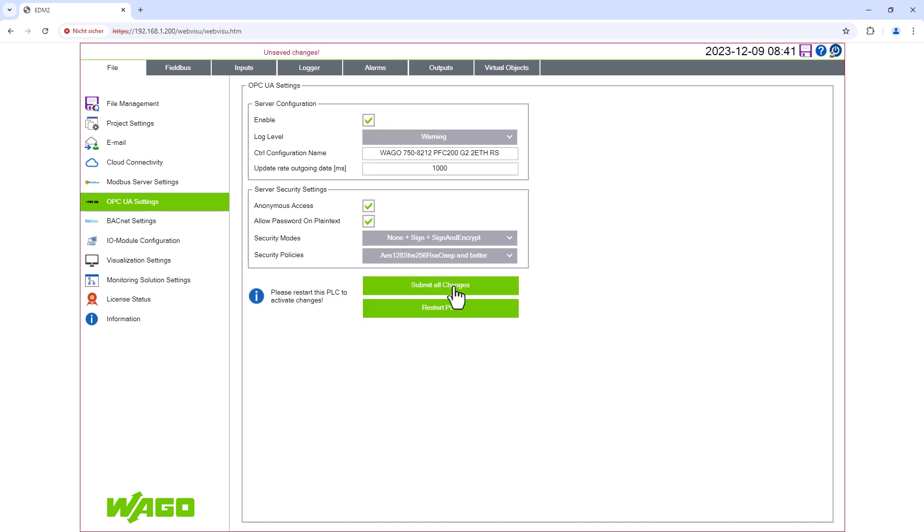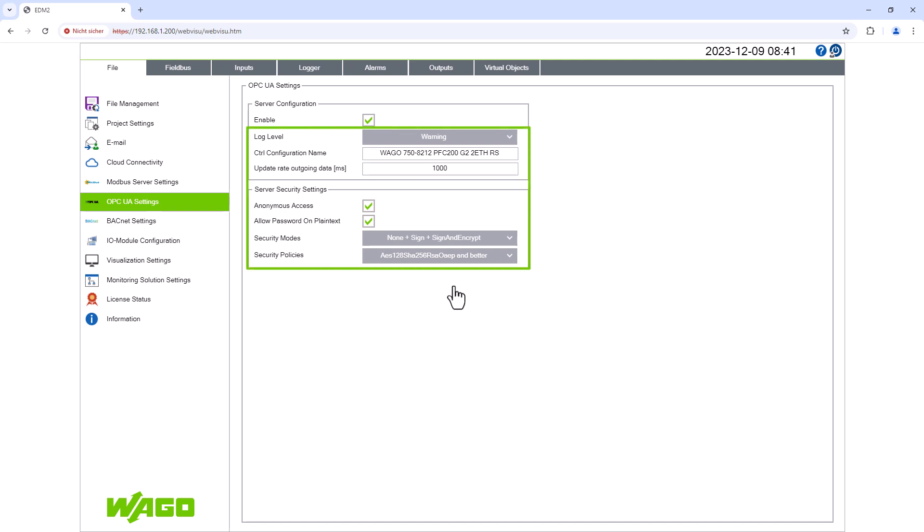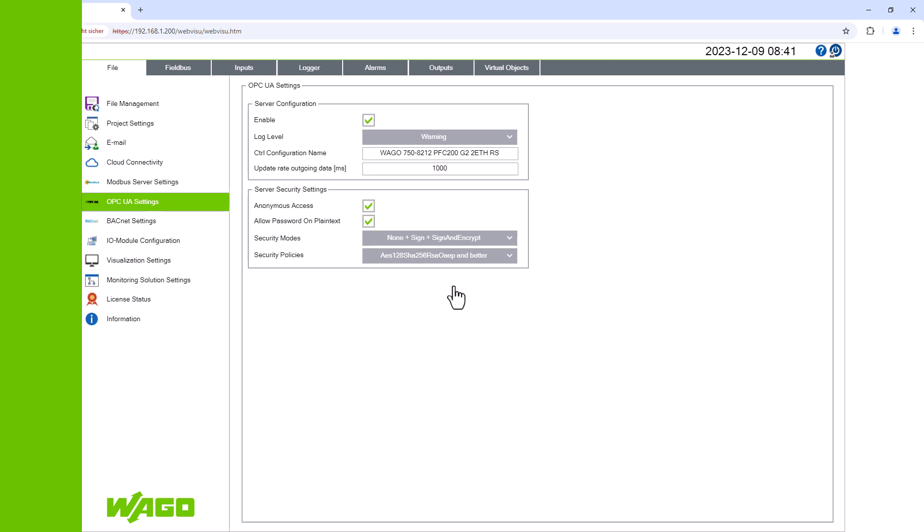Please note that OPC UA takes up quite a lot of memory on the PFC, so we recommend that you only enable OPC UA if it is needed. Below this are all the server and security settings, which we will leave at their default values for this example. This means that everything is already configured in Energy Data Management and our PFC is providing both temperatures via the OPC UA server.